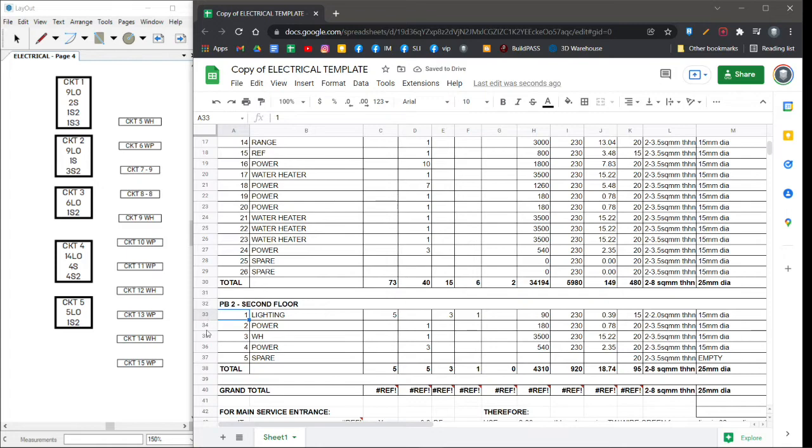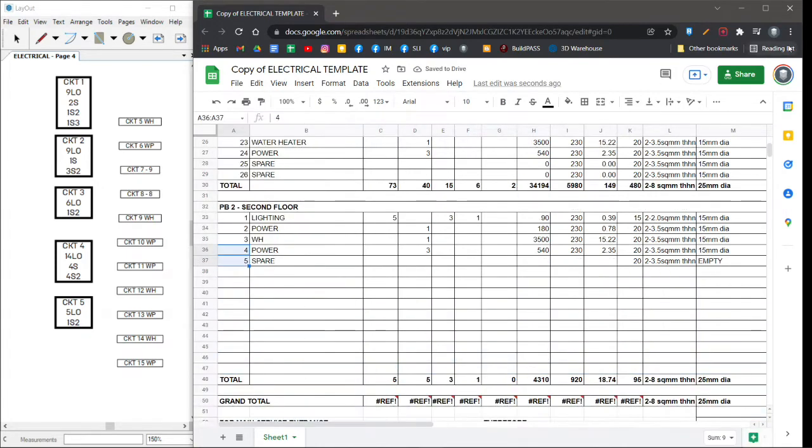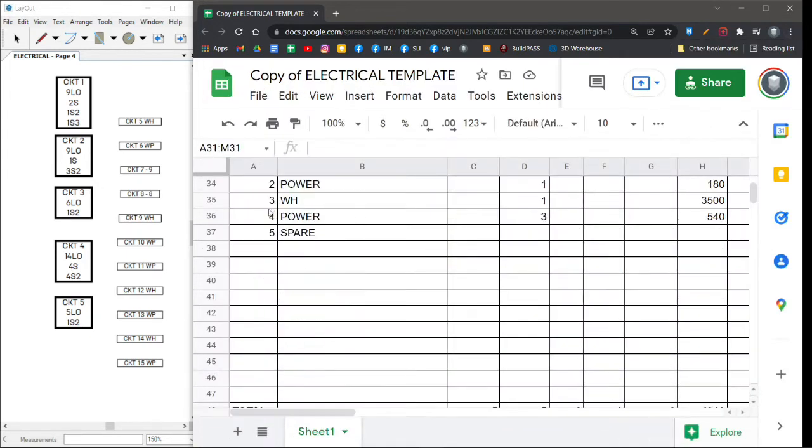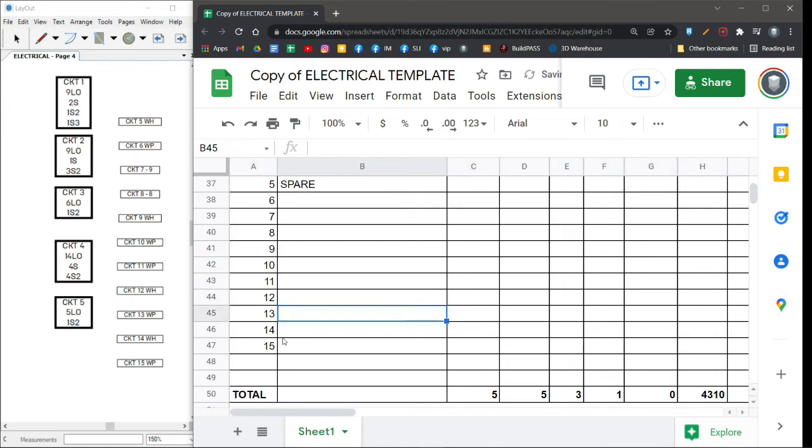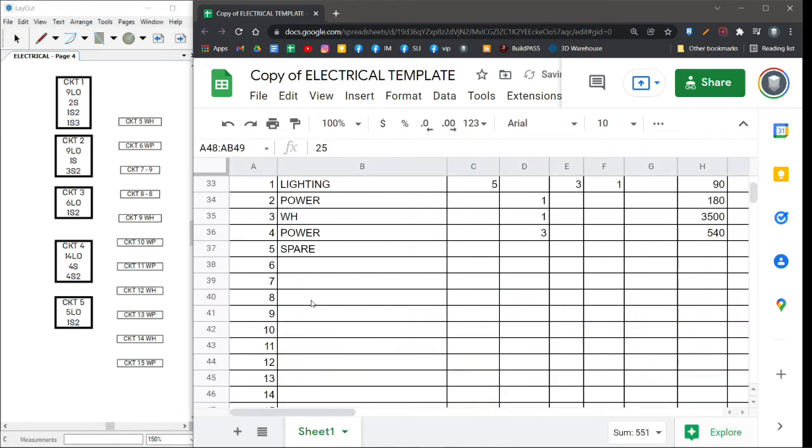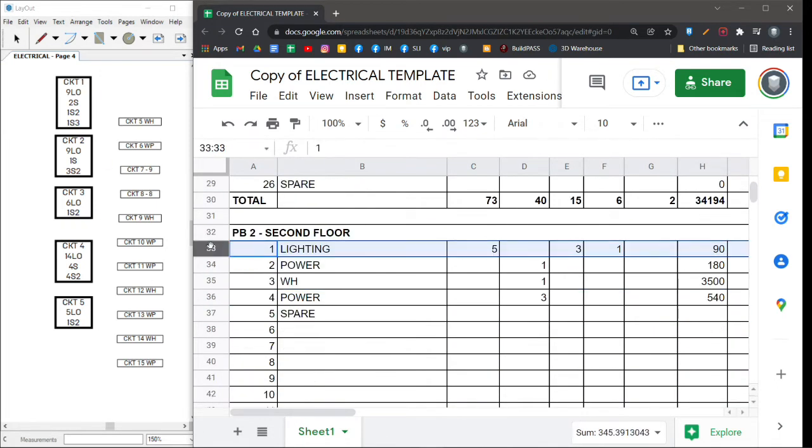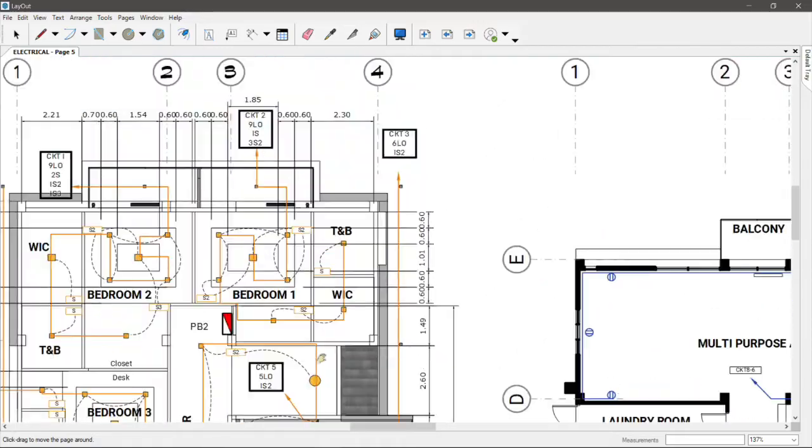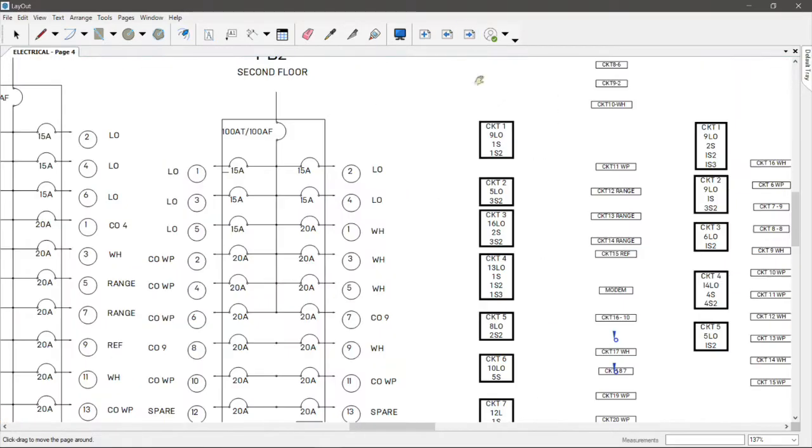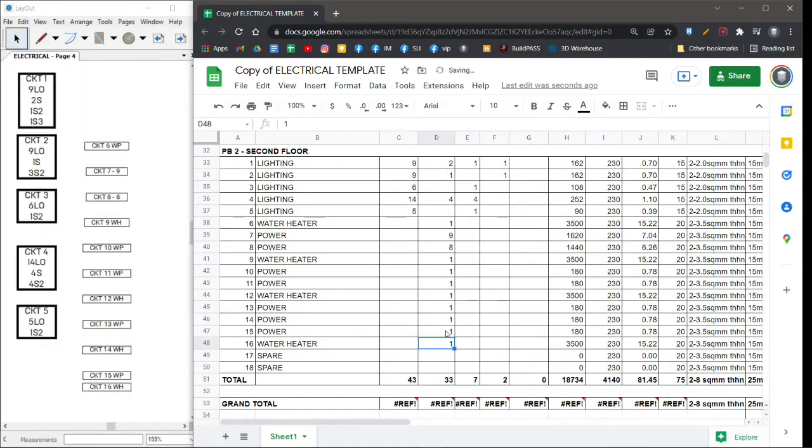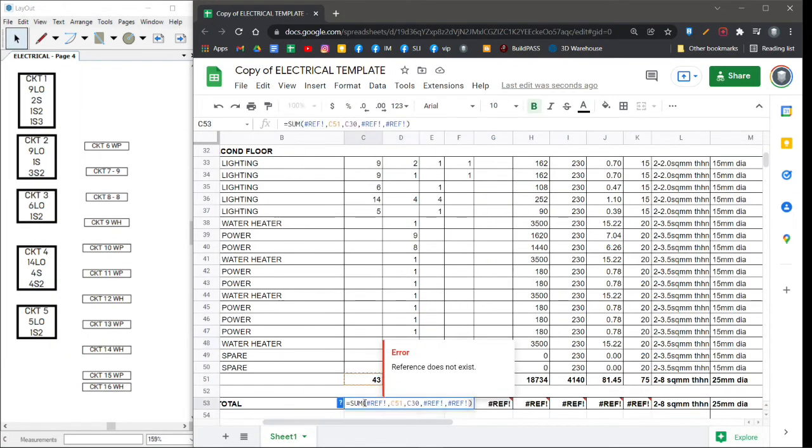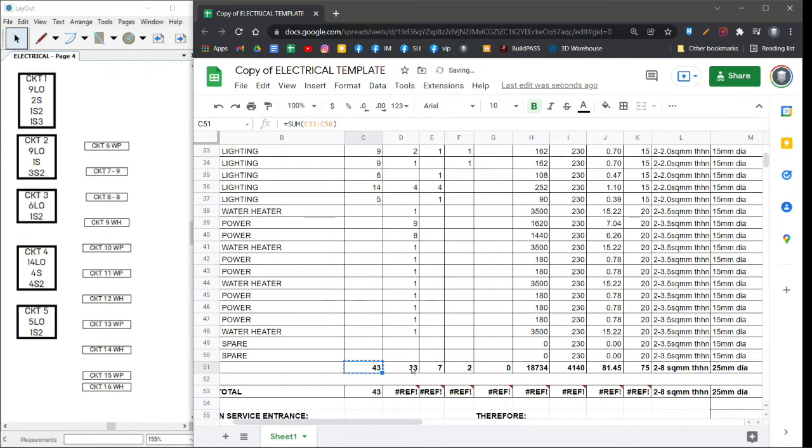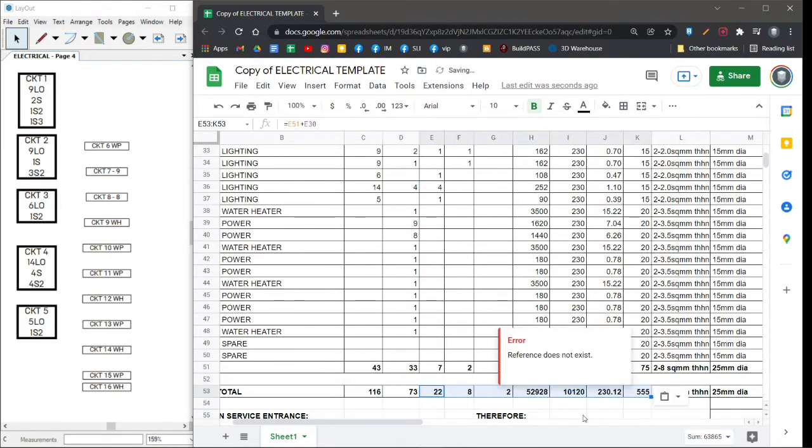Now the difference between the power and lighting is our size of the conduit inside the conduit. Our wire is actually 3.5 while our lighting is like 2.0. So we'll leave the spare blank because we do not know what that will put, but we have to update the value of our water heater, which is actually 3,500. Let's do the same thing for our second floor, which is panel box number two. Let's use the same technique and arrange all the numbers, quantity of lighting, and power outlets as well. Now don't forget that the total will be the summation of all the columns inside the table.